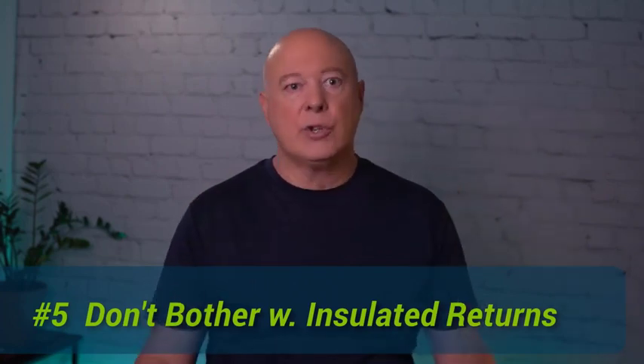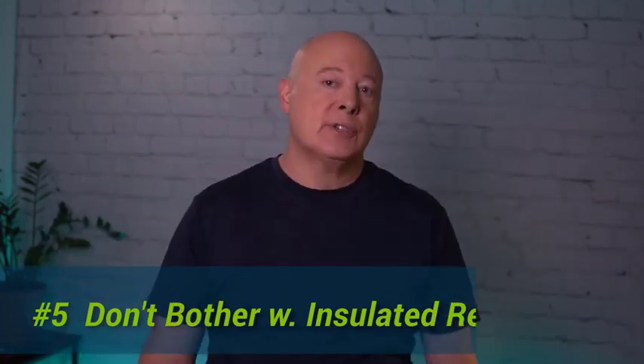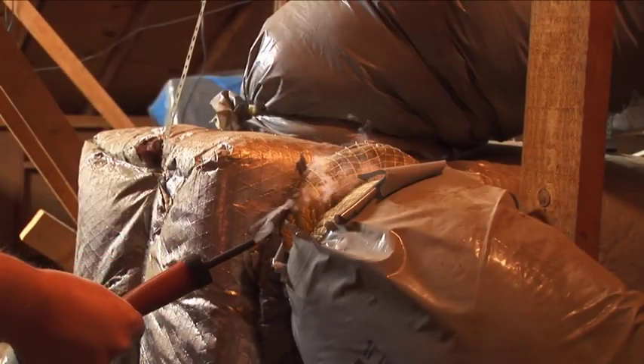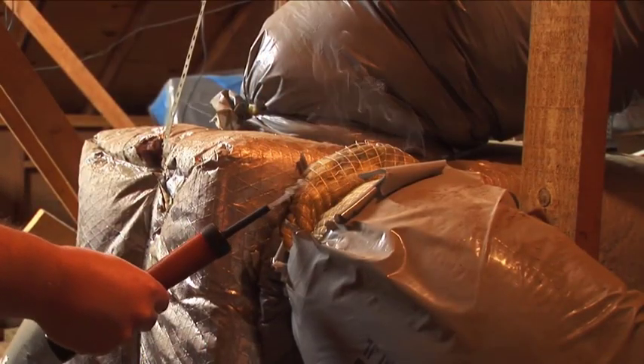Thermal imaging won't show duct leakage going into insulated return ducts, since the insulation masks what's happening when unconditioned air gets sucked into the airstream inside the duct. To show air getting sucked into insulated return ducts, you need to use handheld fog. So, thermal imaging won't show you the effect of air getting sucked into insulated return ducts.